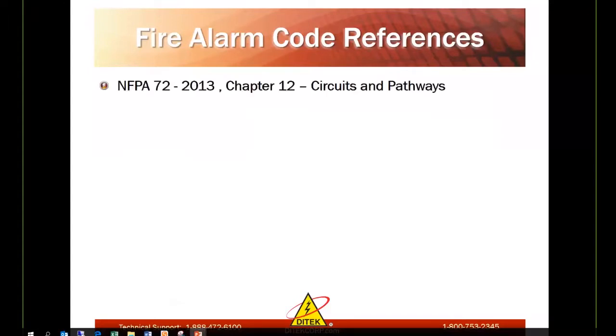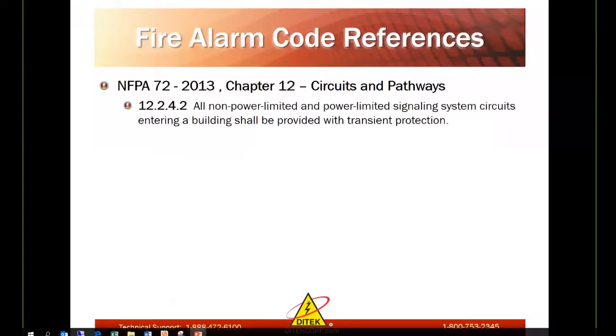Fire alarm code references. It's NFPA 72, 2013, Chapter 12, Circuits and Pathways. This section is all non-power limited and power limited signaling system circuits entering a building shall be provided with transient surge protection.